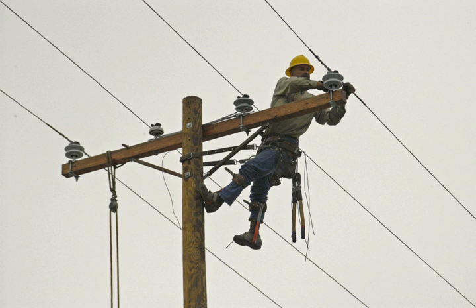Topic. Safety. Lineworkers, especially those who deal with live electrical apparatus, use personal protective equipment (PPE) as protection against inadvertent contact. This includes rubber gloves, rubber sleeves, bucket liners and protective blankets. When working with energized power lines, linemen must use protection to eliminate any contact with the energized line. The requirements for PPE and associated permissible voltage depend on applicable regulations in the jurisdiction as well as company policy.